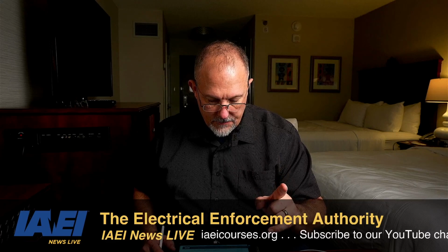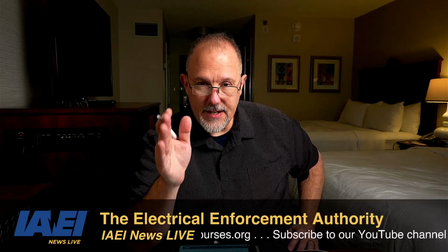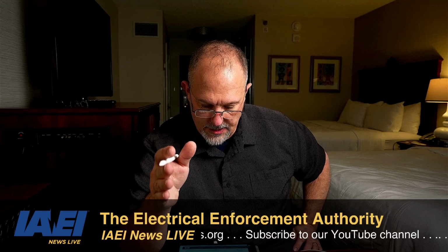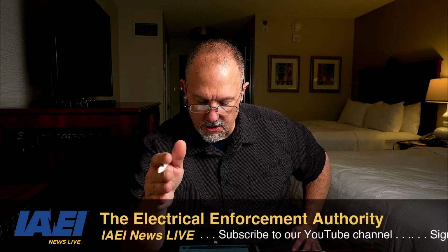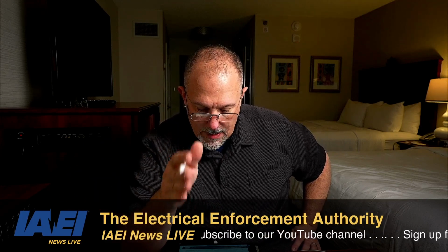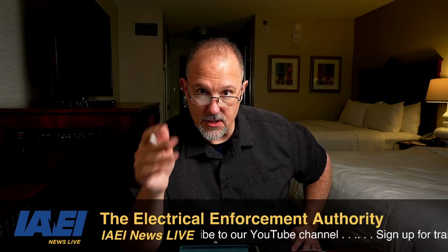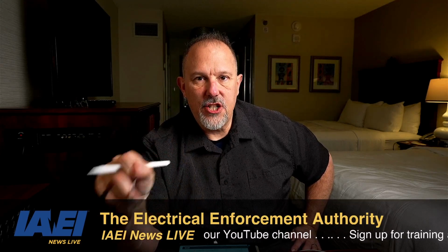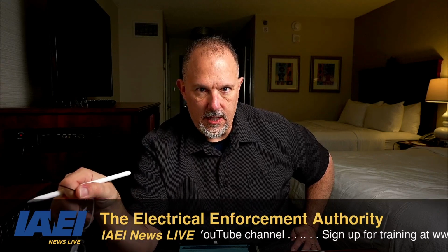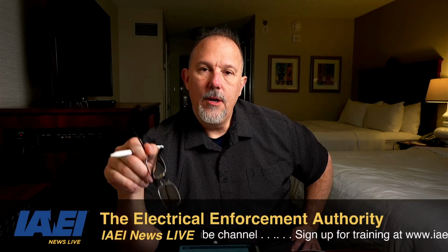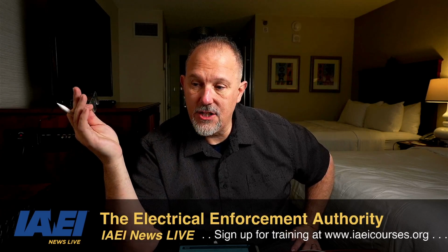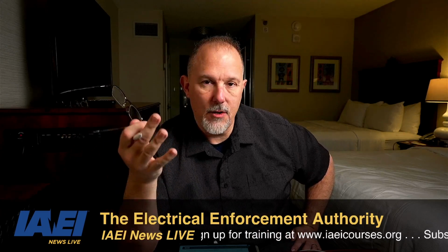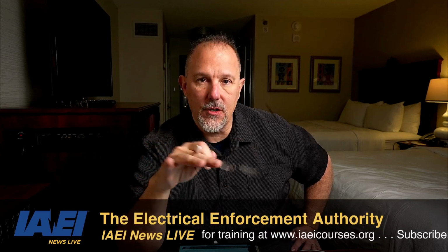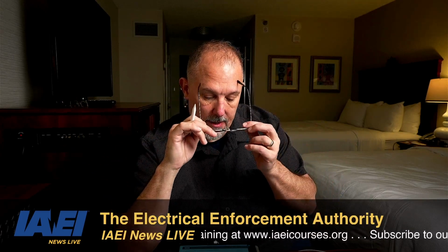First, let's talk service. The definition of service is the conductors and equipment connecting the serving utility to the wiring system of the premises served. An on-site generator is not a utility. So that equipment, when you feed the generator to, say, a transfer switch, or if you were putting a load on the generator, that equipment is not service equipment.